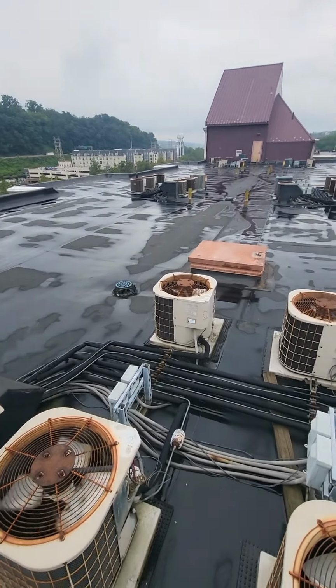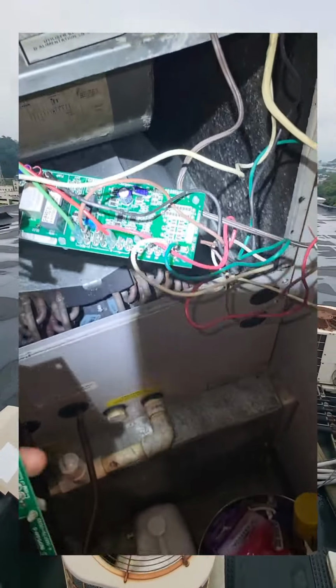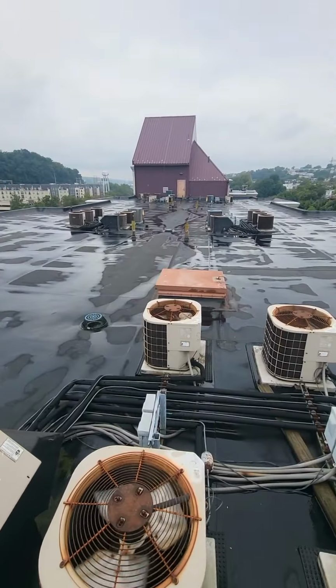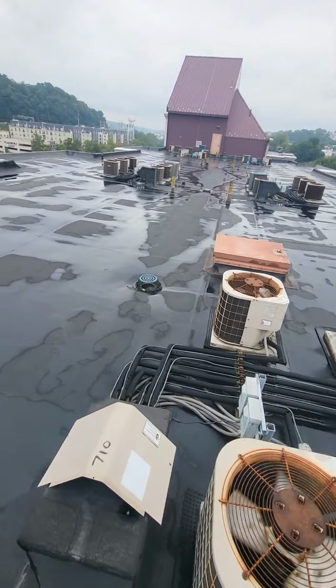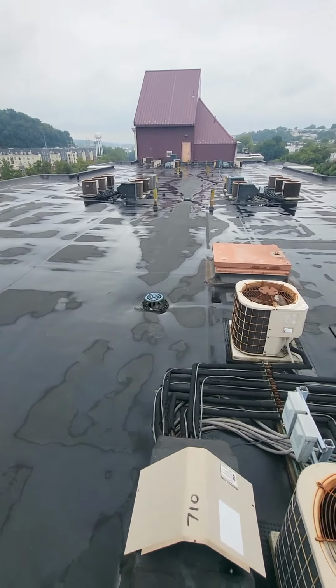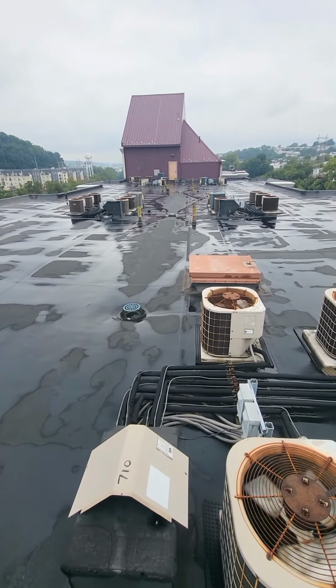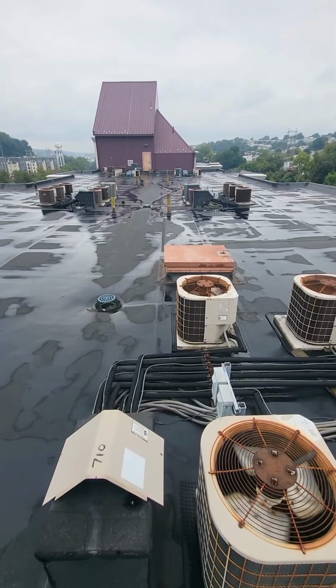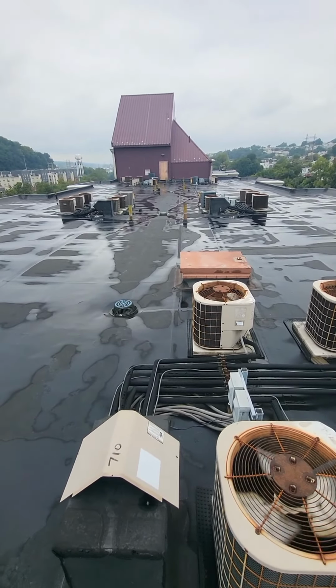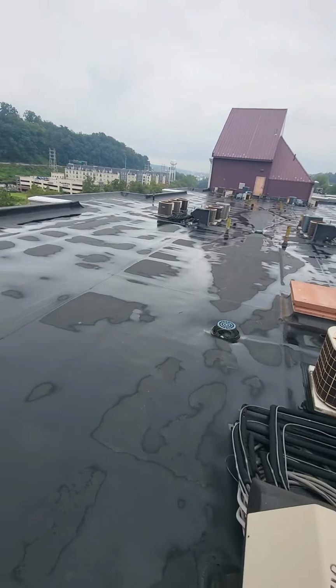One of the relays was burnt up, and as you guys can see in the picture, that picture, like I said, that you see of the burnt relay, that's enough that will trip the breaker that will trip the fuse every single time we turn power on to that unit. So as a result, guys, even with a new transformer and a new fuse, that board was so shorted out that no matter what you did, the fuse is going to trip without the unit even running.